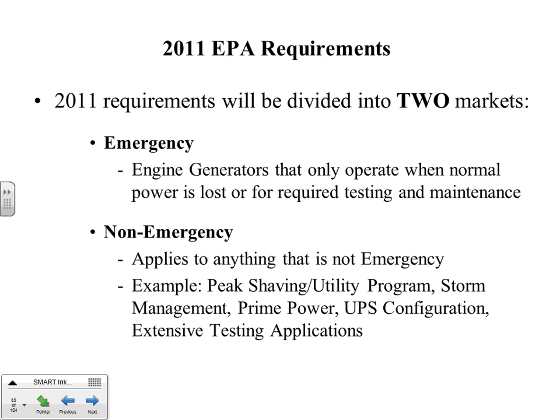Non-emergency is everything else, and those things that are non-emergency examples: peak shaving utility programs. This has a lot of people upset. Storm management. What that is: a lot of companies that had generator sets, if they saw a thunderstorm coming, rather than take a break in power when they weren't expecting it, set their equipment up to where they could accept a transfer, and they would actually run their generator set. They call it avoidance, interruption avoidance. So storm management is another term for that. Prime power, where there is no utility, is non-emergency. UPS configuration and extensive testing applications.